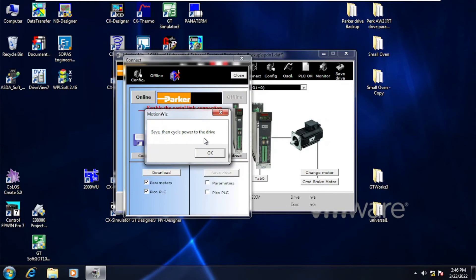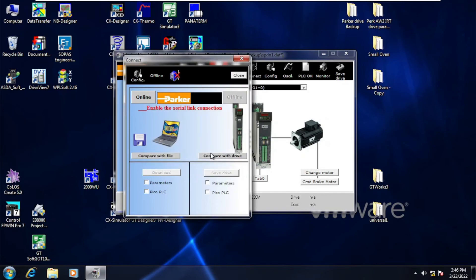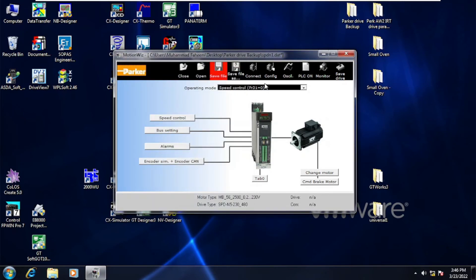It is now saying to save then cycle power to the drive. If you click OK it will automatically save, but you must power up the Parker Drive again for the changes to take effect. Click OK, and when you power up the drive again, the file backup will be saved permanently to the Parker Drive.